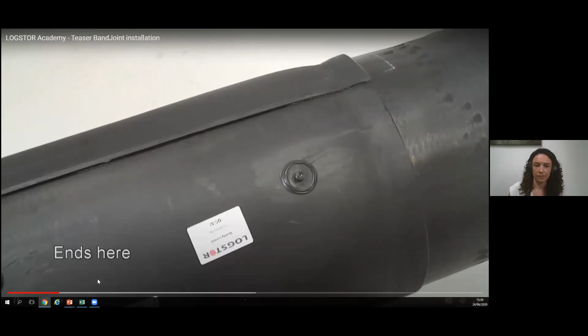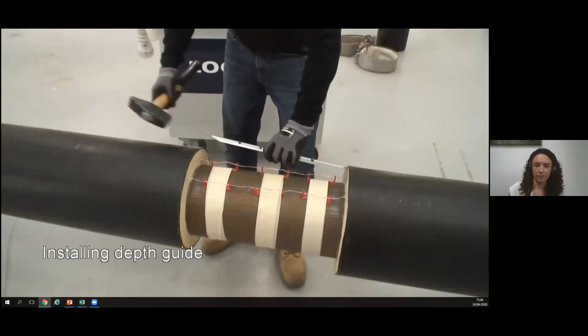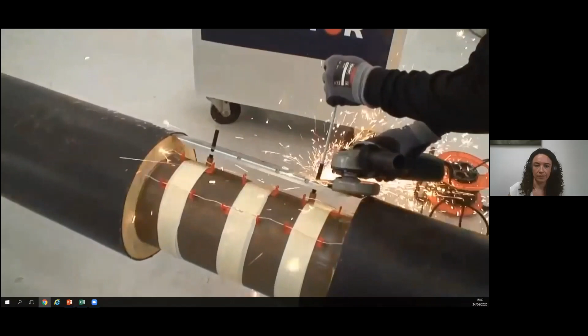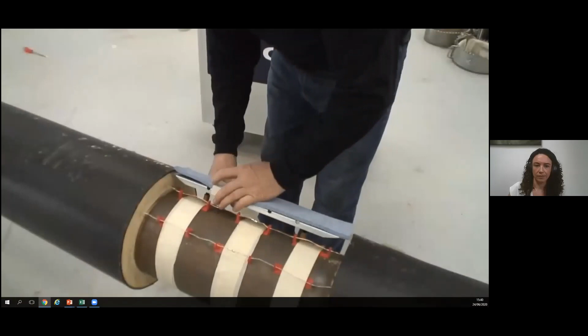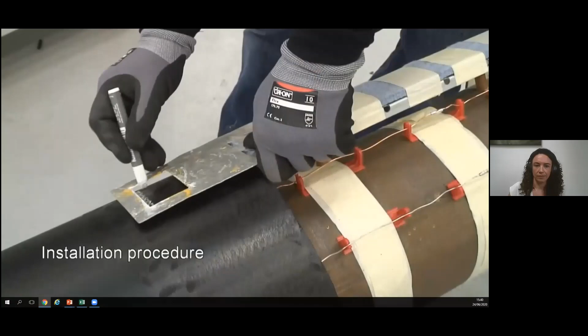So basically these are the wires that are pulled across to continue the leak detection system. We put in a depth guide. Those then have spacers to keep that depth guide from pushing into the pipe and keep that nice and constant and the whole thing rigid. Those are cut off once they're at the correct length, and then that's taped with some foam to protect the casing. Cleaning and abrading is absolutely essential when it comes to band joint fitting.